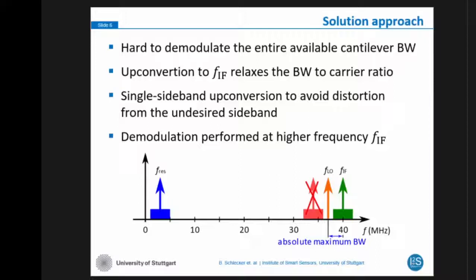It is quite hard to achieve this demodulation to use the entire bandwidth of the cantilever. What we do to achieve this is use an upconversion of the baseband signal onto a higher intermediate frequency. The demodulation is performed at this higher intermediate frequency: the original cantilever resonance frequency and the signal band around it is converted by the LO frequency to the higher IF frequency. We implement single sideband upconversion to avoid the second unwanted sideband and to avoid the use of sharp filters at the intermediate frequency.